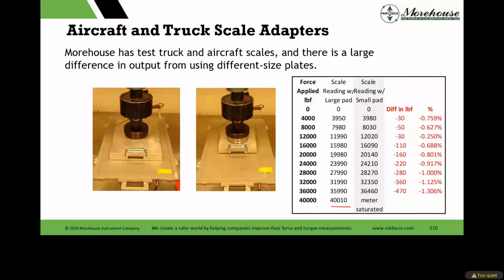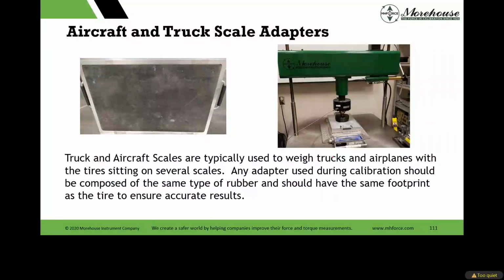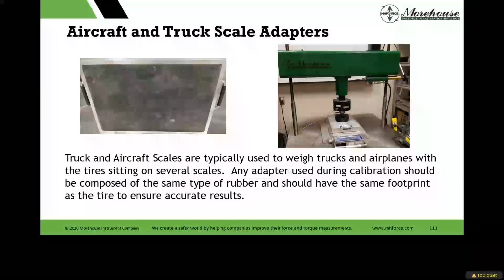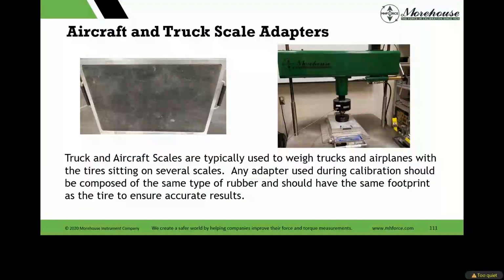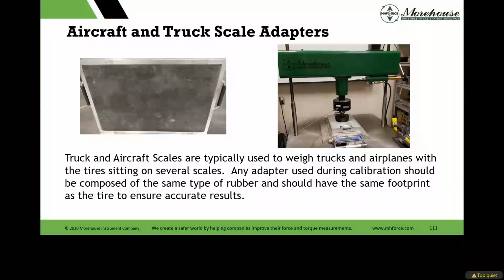What you want to do if you're doing any truck or aircraft scale is look at the product manual, and hopefully the manufacturer has recommended guidance of what size the adapter should be. The adapter that's used during calibration should be composed of the same type of rubber and should have really the same footprint as the tire.